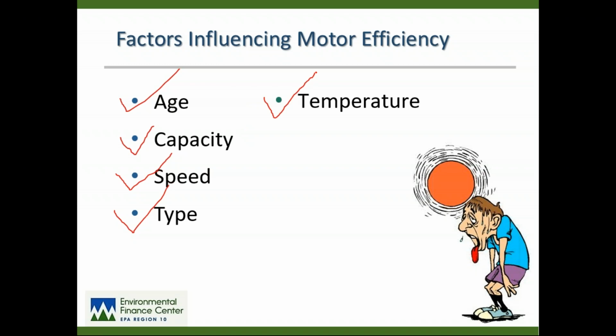Temperature is a motor's greatest enemy. The whole idea is to keep the inside of a motor cool. As temperature increases, electrical resistance increases, and efficiency goes down. If you have your motor rewound, which many systems do, it can be very economical to go and have a motor rebuilt. And basically by rewinding, we mean taking it to a motor shop, having the end bells pulled off, all the bearings taken out, and an attempt made to stuff all the copper windings back into that motor that came out of it. That's what we call rewinding. And it generally gives you an almost brand new motor, but you will lose some of the efficiency that the factory put into that motor if you have your motors rewound.